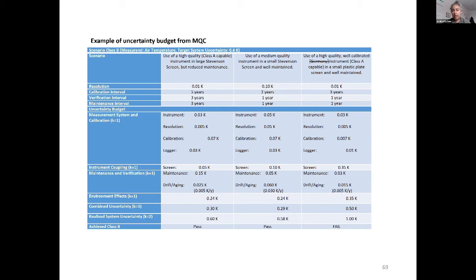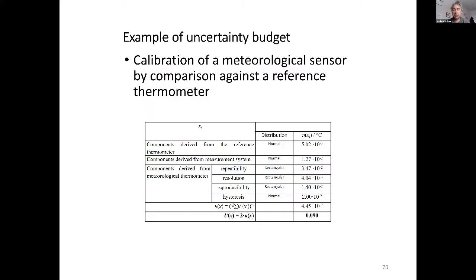It's nice. It's a way which gives you some scenarios, and it gives you a way to include some of the quantities we have and to have an overall uncertainty. This is another example. It's taken from the calibration against a reference 1. And you see in the last 2 lines, we got everything. We have to clearly say which is the distribution. You have components in groups, 3 groups of components: the repeatability, the resolution, and so on. For example, the resolution is rectangular. Of course, it's within this and that, equally distributed. And then you have the double value.